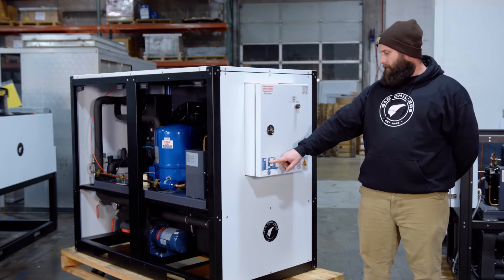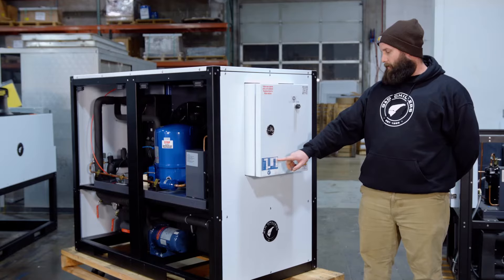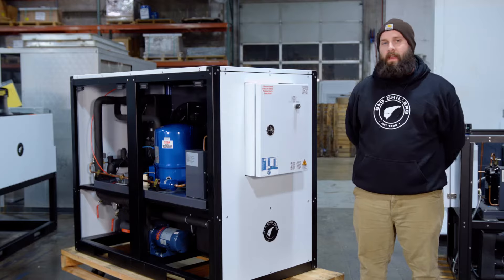For instance, this MCA is 42.3 and this MOP is 69.2. So if I was sizing a breaker for this chiller, I would go with a 50 or a 60 amp breaker.